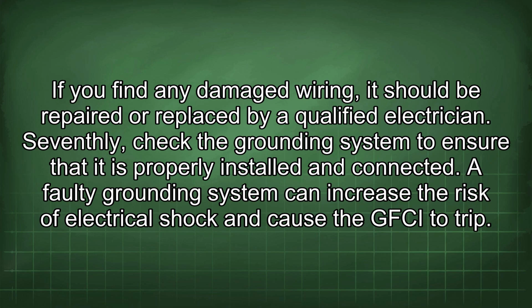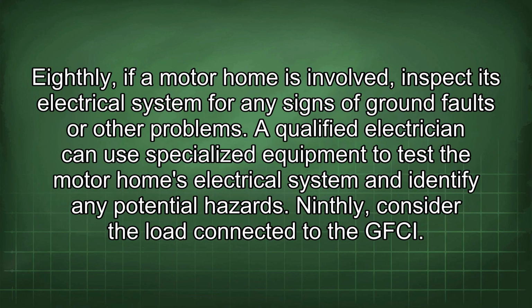Seventhly, check the grounding system to ensure that it is properly installed and connected. A faulty grounding system can increase the risk of electrical shock and cause the GFCI to trip. Eighthly, if a motorhome is involved, inspect its electrical system for any signs of ground faults or other problems. A qualified electrician can use specialized equipment to test the motorhome's electrical system and identify any potential hazards.